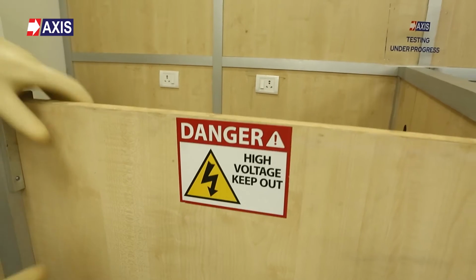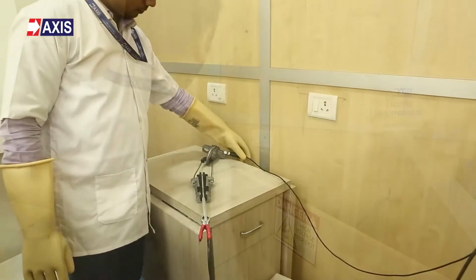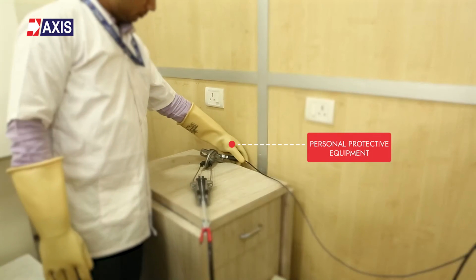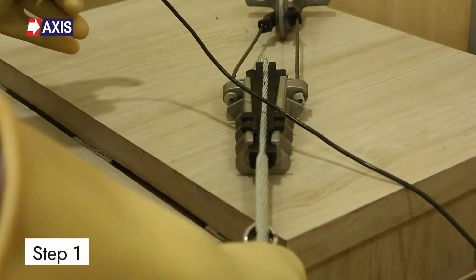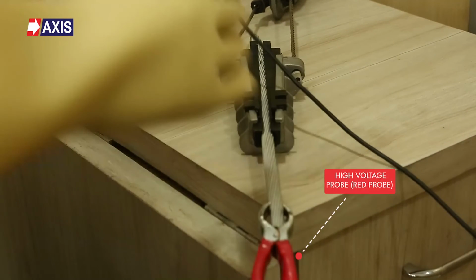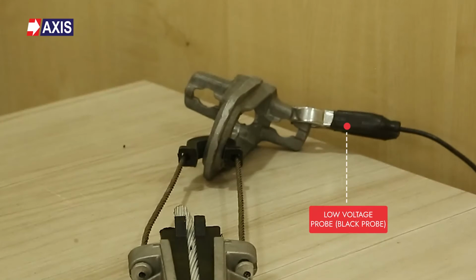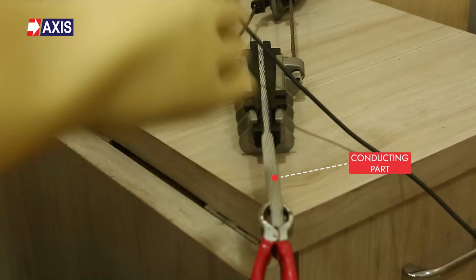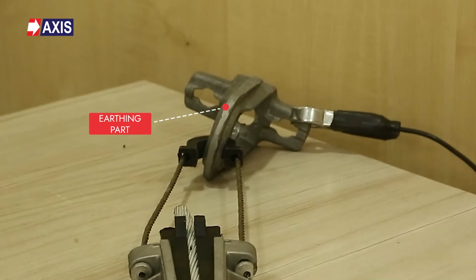Secondly, please ensure that all individuals use proper tools, procedures and personal protective equipment to avoid injury. Step 1. Connect the high voltage probe, the red probe, and the neutral probe, the black probe, to the sample. The high voltage probe will be connected to the conducting part of the sample and the neutral probe will be connected to the earthing part of the sample.